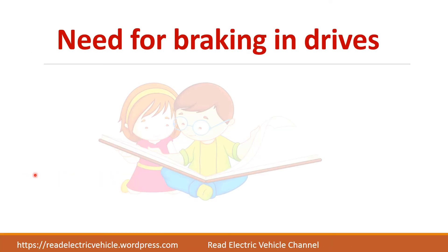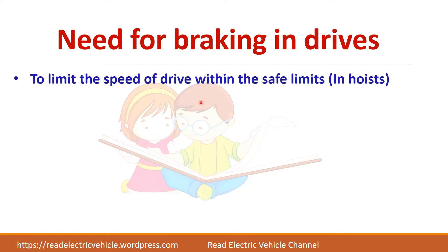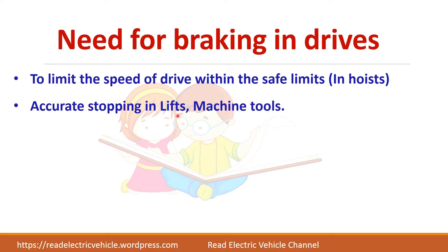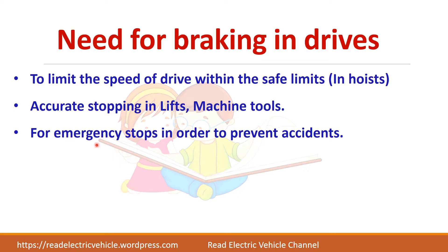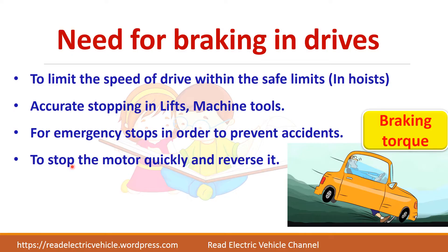What is the need for braking in drives? First, to limit the speed of the drive within a safe limit. For example, take a hoist which is carrying a heavy load from top to bottom. In such cases, due to gravitational force, the load may reach the ground level at a very high speed. To avoid any accident, you have to limit the speed within a safe limit. In some applications like a lift, it is necessary to stop exactly at the floor level. And in case of emergency, we have to stop the drive. In some applications, we may need to reverse the direction of the drive, so in such cases, you need braking.